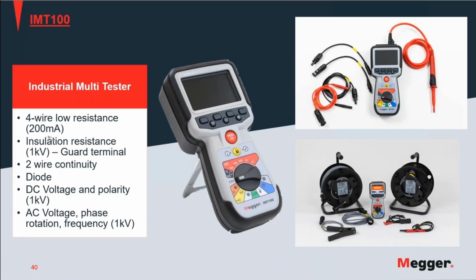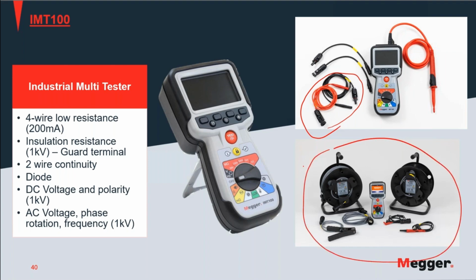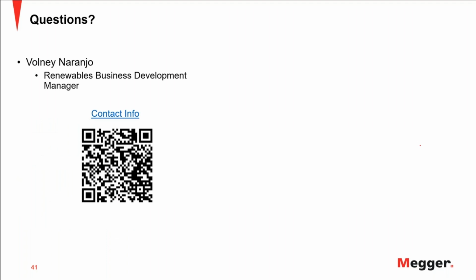So with that, I am finishing the presentation. I want to talk about this instrument, the IMT 100, which is a Megger industrial multi-tester. In addition to other tests, it mainly can do the insulation resistance test and the low resistance measurement, and of course it can do a continuity test. The 4-wire measurement method it can do with 200 milliamps, and you have multiple accessories to connect to the MC4 terminals to measure the insulation resistance, or you have the reels to do the 4-wire measurement for a bonding verification. With that, I've completed the presentation and am ready for questions if there are any.